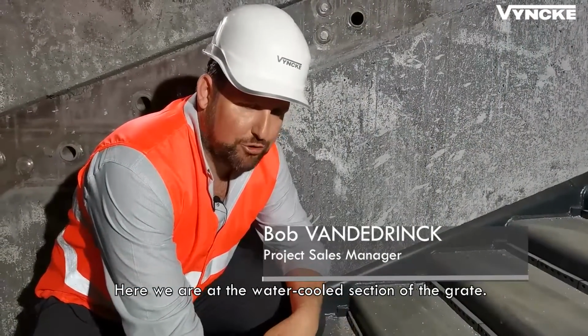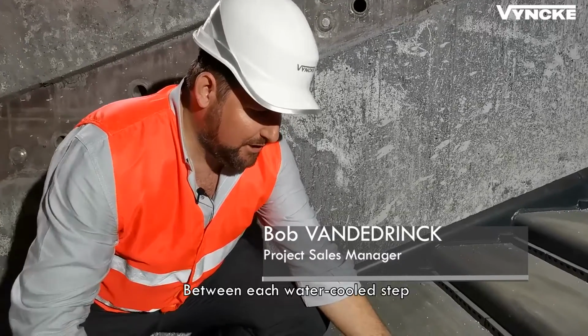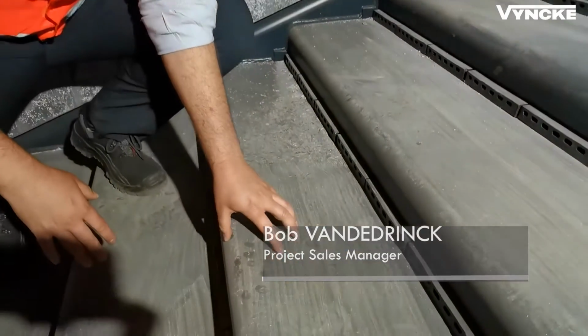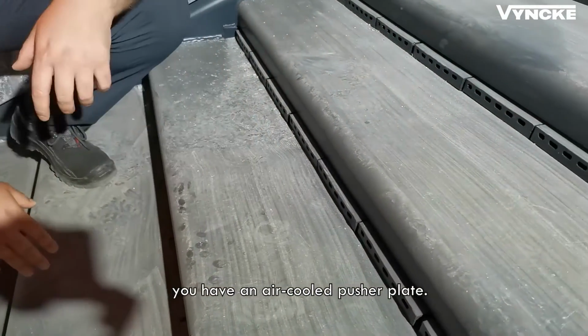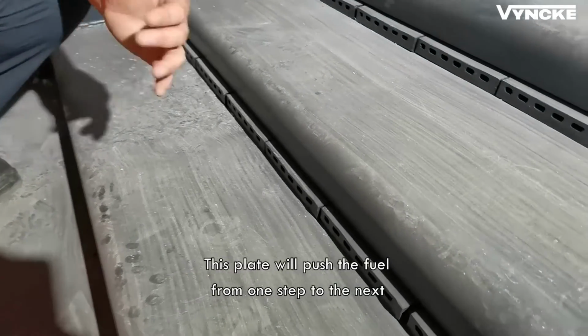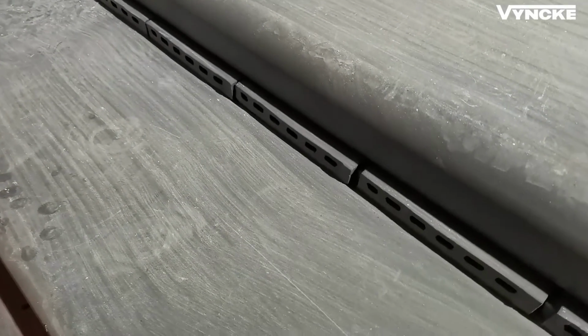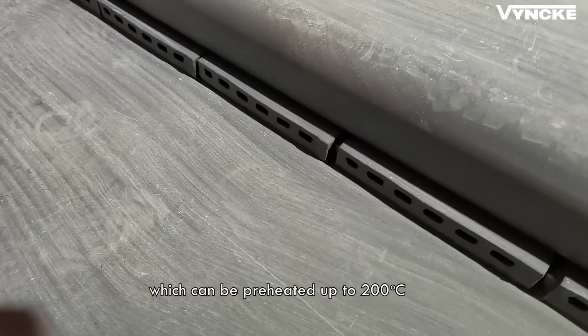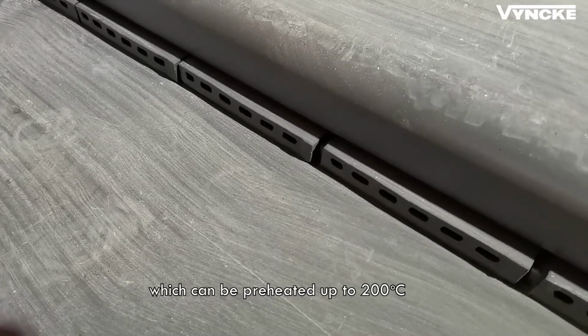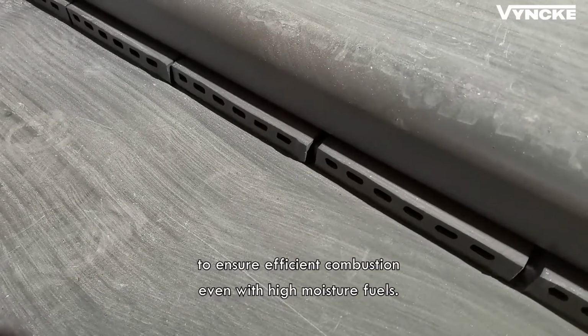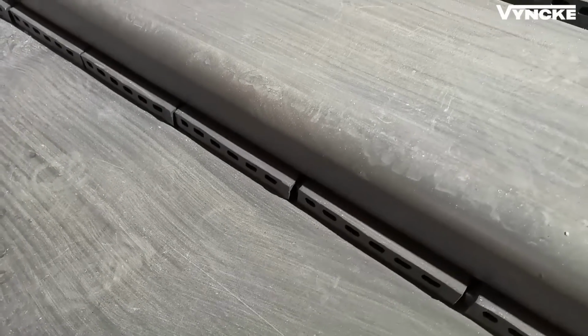Here we are at the water-cooled section of the grate. Between each water-cooled step, you have an air-cooled pusher plate. This plate will push the fuel from one step to the next, as well as feeding the primary air, which can be preheated up to 200 degrees to ensure efficient combustion, even with high moisture fuels.